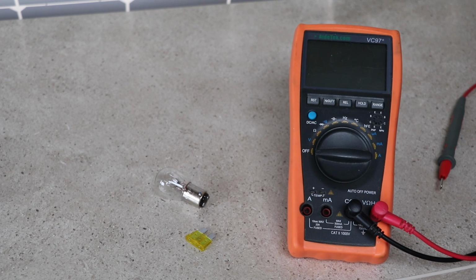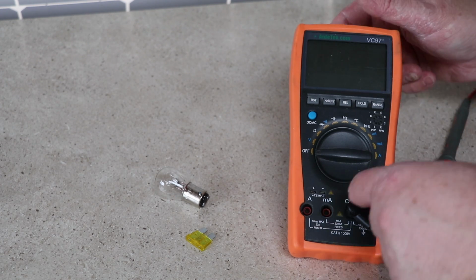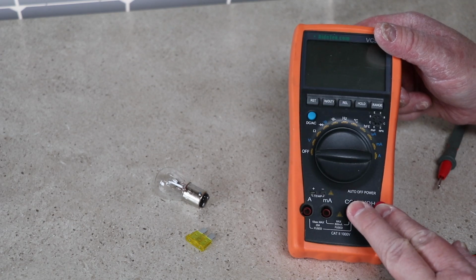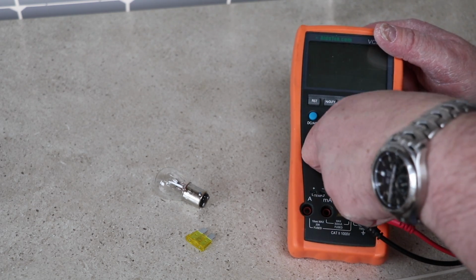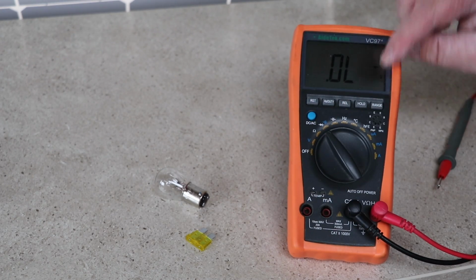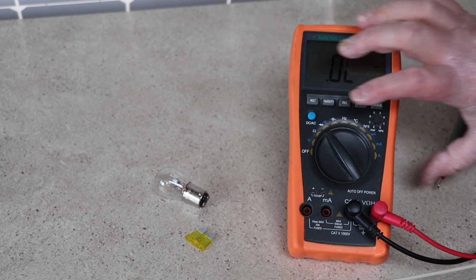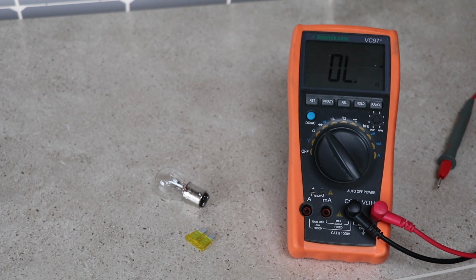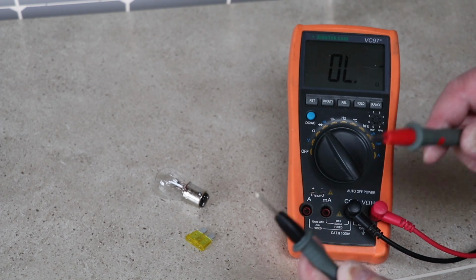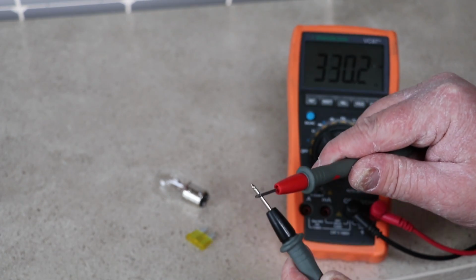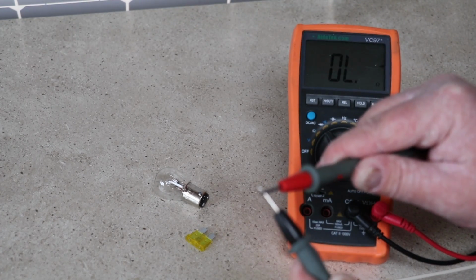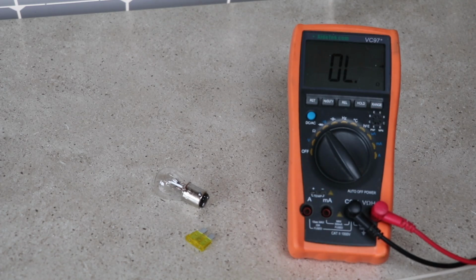This one is really straightforward, and in actual fact we don't need to use the display for this. Depending on the meter, it may make a sound, it may not. We need to make sure our probes are in the correct sockets, put our meter round to this audio sign, press the function button so we can hear something. And very simply, if I put the two probes together, you can see that we've got continuity.